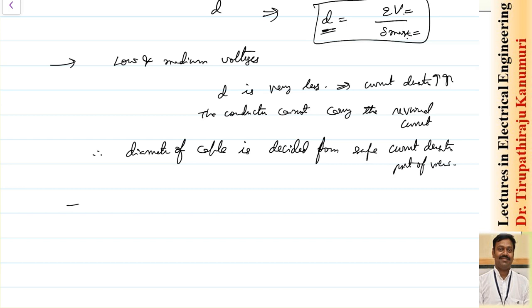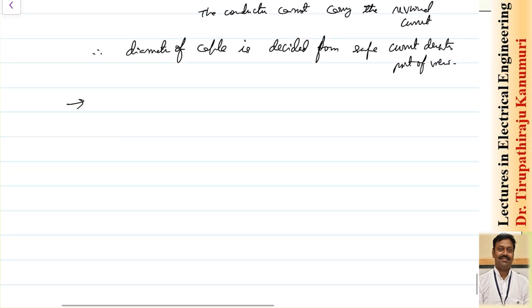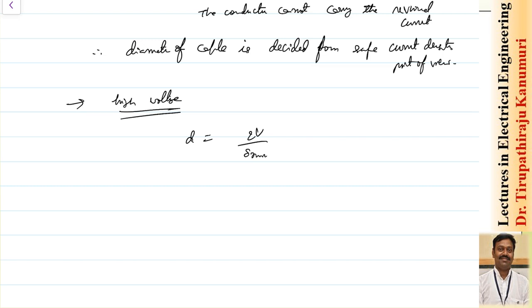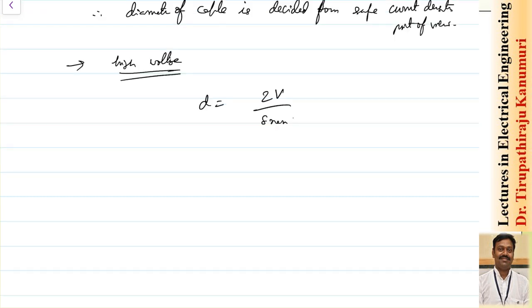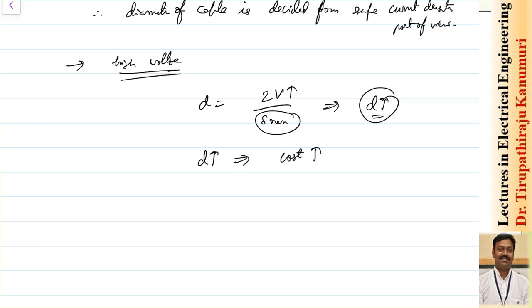For high voltage cables, as voltage increases, d = 2V/g_max gives a larger diameter than what is needed for current-carrying capacity. This excess size increases conductor cost and cable weight. To address this, different techniques are used.